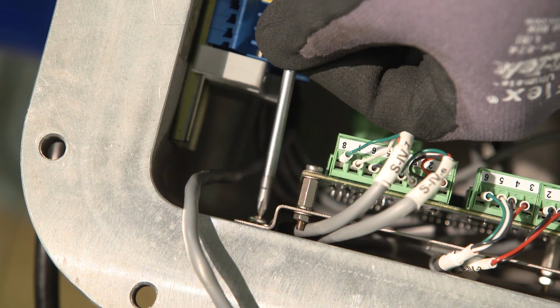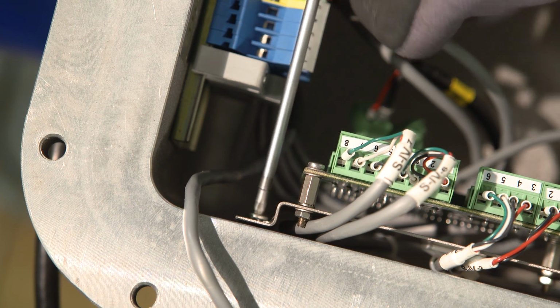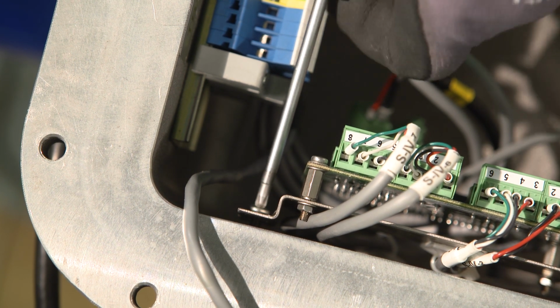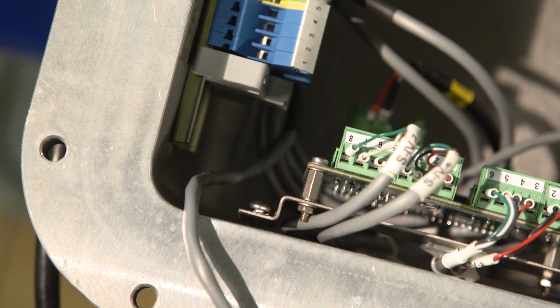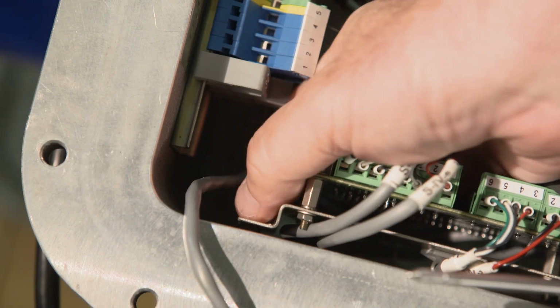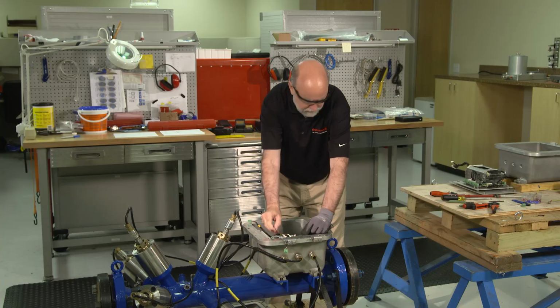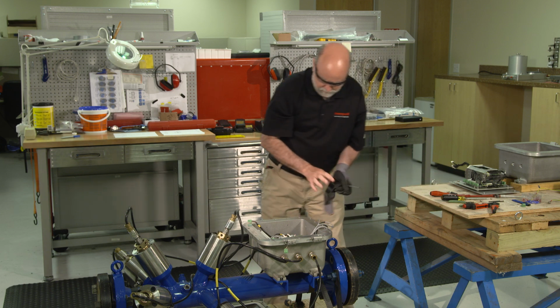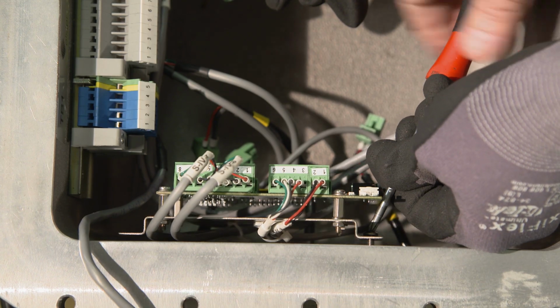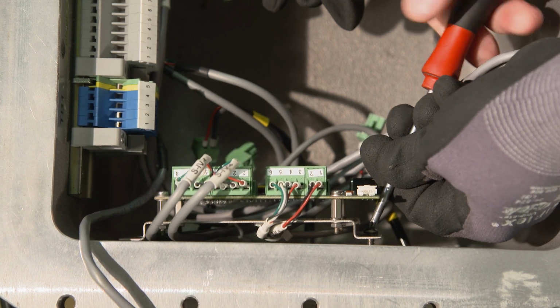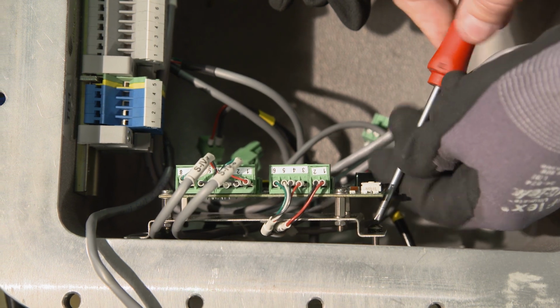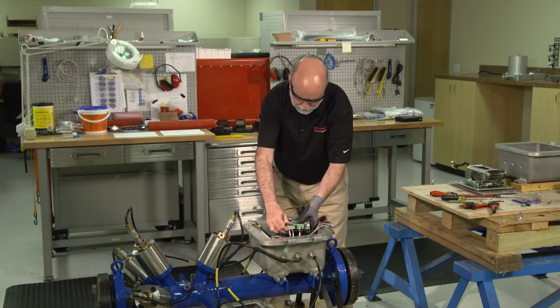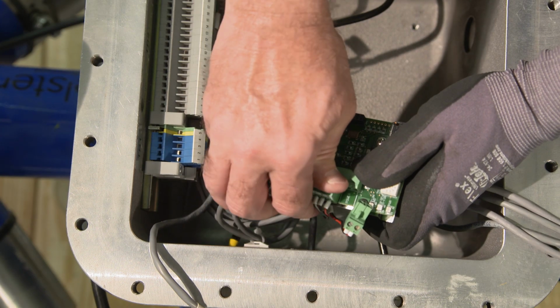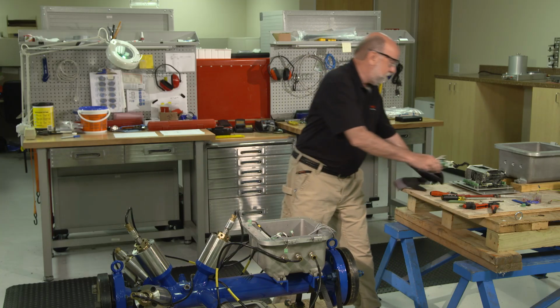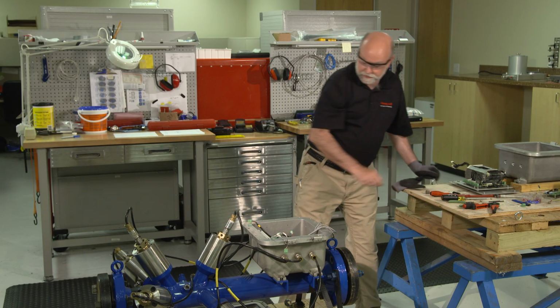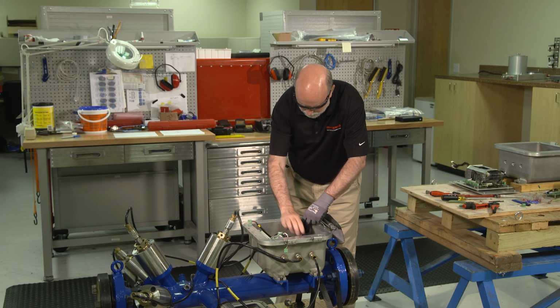We have this frequency controller, F3. This is an FC3 card over here. I'm going to remove the screws that hold the bracket into the box. It may be necessary to take the card off of the bracket first to be able to reach both of the screws. And we're going to just unplug all of these wires. I'm going to set that aside. Again, we're not reusing any of that equipment.